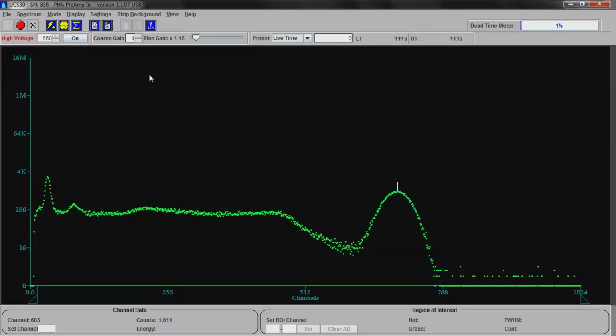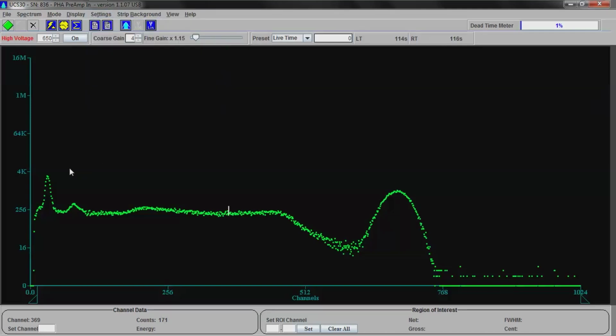To do this simply, we can stop this, and technically speaking, go to energy calibration and click the auto calibrate button. If we did this, the machine would automatically calibrate it for us, but we're not going to do that today. We're going to manually calibrate. Now here's how we do it. We come here and look at this peak right here, and we're going to find probably the highest point on it, which looks to be about channel 31, channel 32, somewhere in there. We'll pick 32.